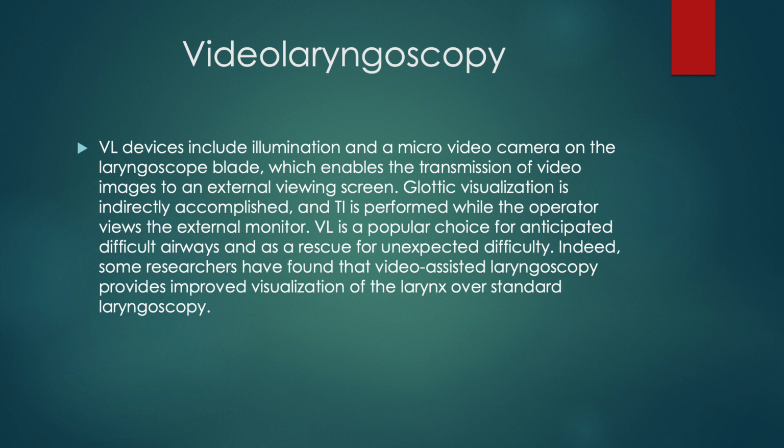One thing that you're going to see is as there's a push for more and more disposable laryngoscopes, video laryngoscopy is cheaper. Okay, it's cheaper because blade replacement for McGrath is like $6 to $12 depending on which one. The disposable laryngoscopes are like $12 to $15, and then if you don't get it with that, you then go to the McGrath. But the number one rescue for a failed video laryngoscopy is direct laryngoscopy.